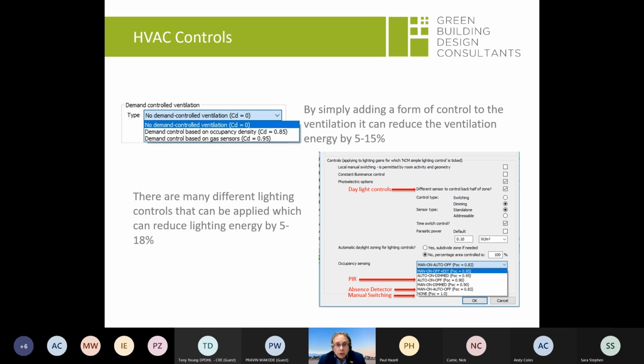And that could be done centrally, or it could be done at a floor level - we would recommend you do it at a floor level. So there'll be motorized dampers that shut down each floor, recognizing when there's low occupancy at lunchtime, nobody's in the building, weekends, or just times generally of low use. That can have a factor of, say, between 5 and 15% reduction on the fans' power.